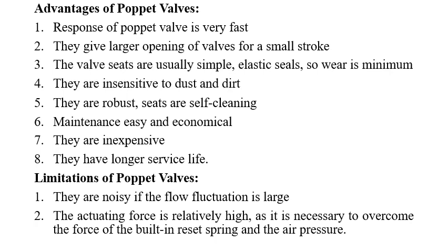Then the actuating force will be relatively high, as it is necessary to overcome the force of the built-in reset spring and the air pressure. See here, the force required to actuate the valve should be more than the spring force, right? At the same time, to hold it, the pressure should be more than the air pressure, so the actuation force required is more for these kinds of valves.